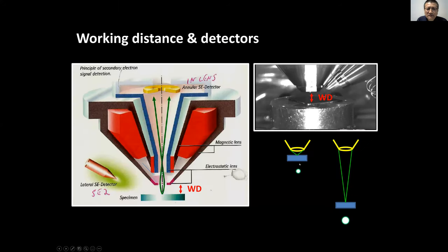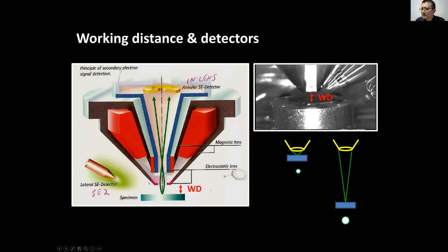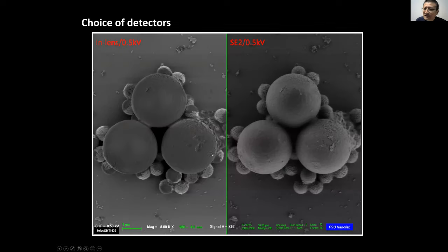Inside the SEM we have two main detector types. The in-lens detector is inside the column — that's why it's called in-lens. The other is called SE2, which is outside the column. Because they're at different locations, they give you slightly different information. Let's compare what the two detectors can do.